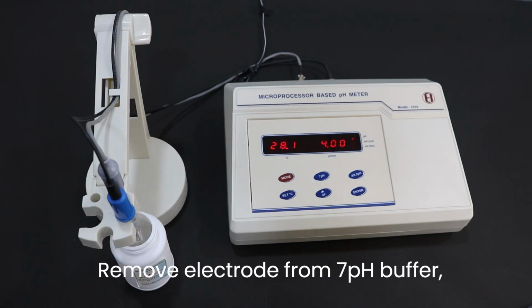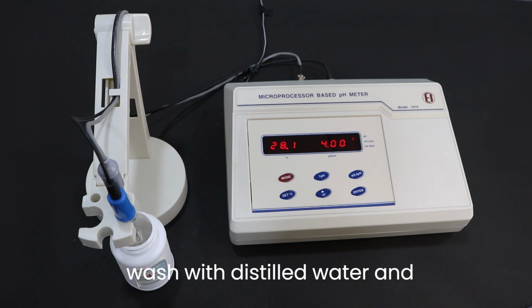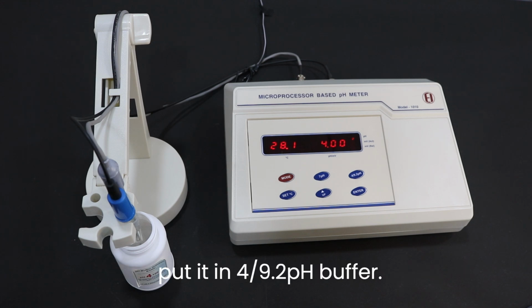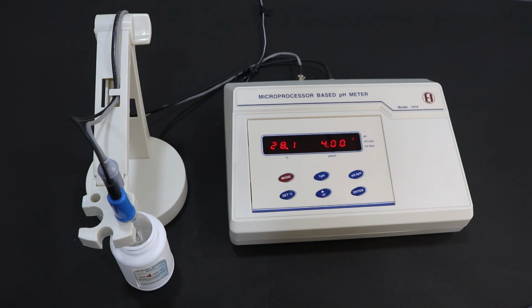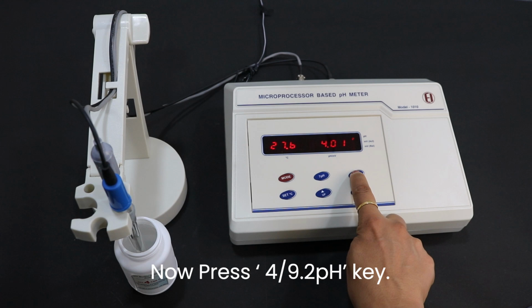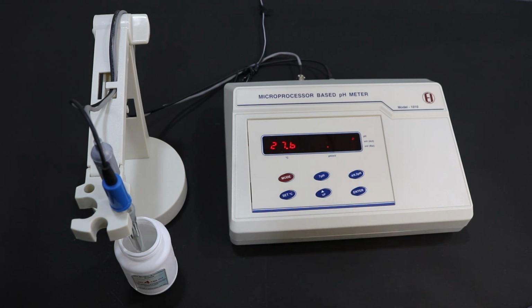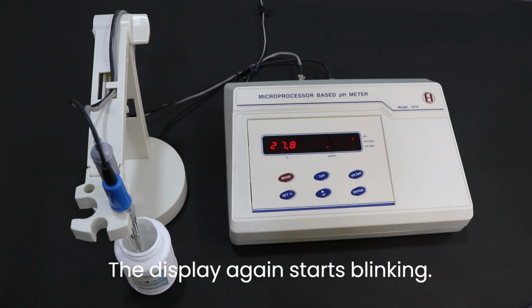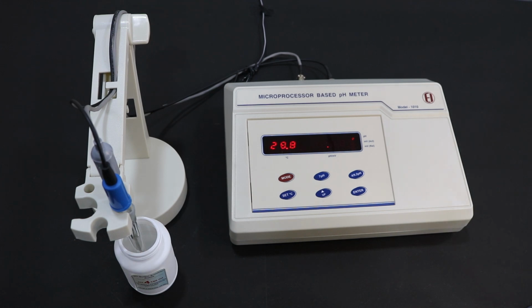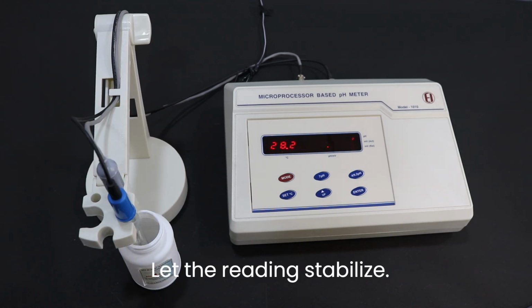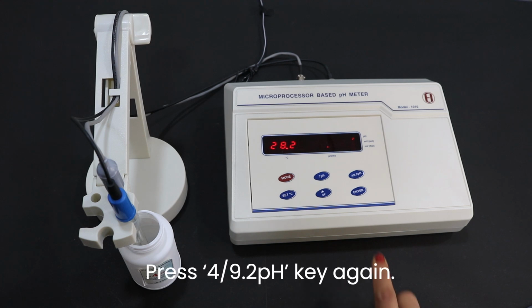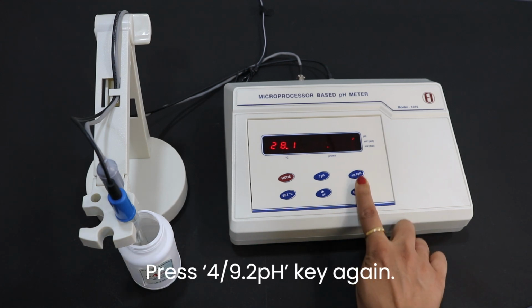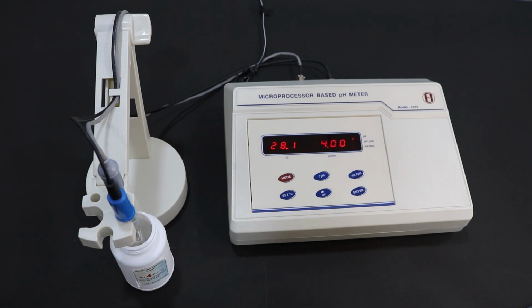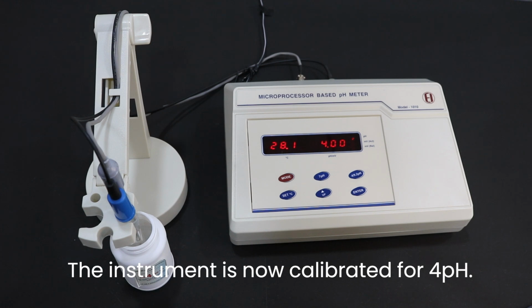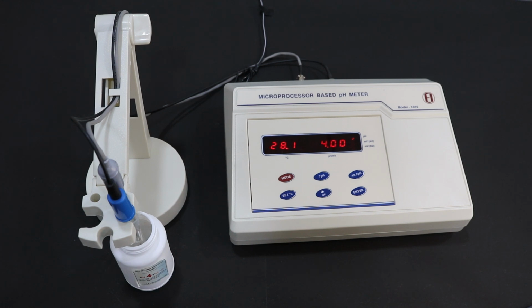Remove electrode from 7 pH buffer, wash with distilled water and put it in 4/9.2 pH buffer. Now press 4/9.2 pH key. The display again starts blinking. Let the reading stabilize. Press 4/9.2 pH key again. The instrument is now calibrated for 4 pH.